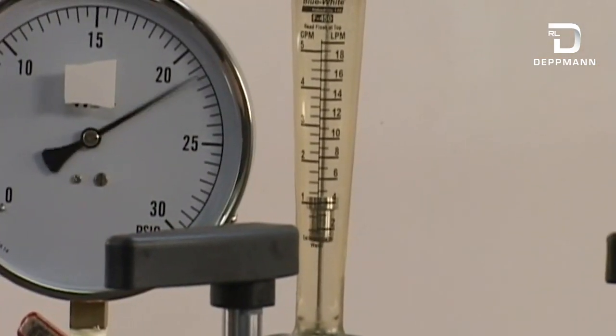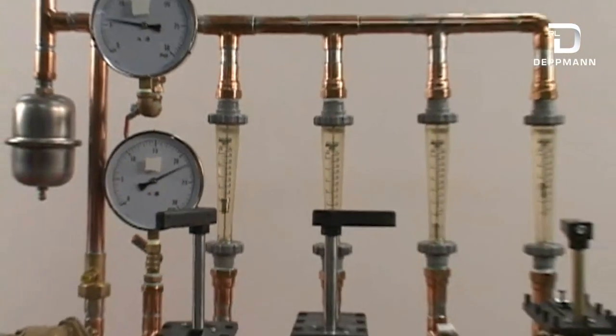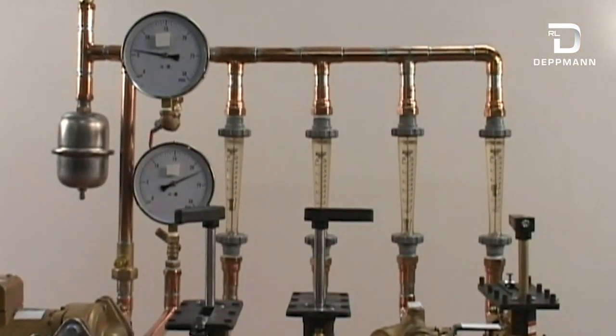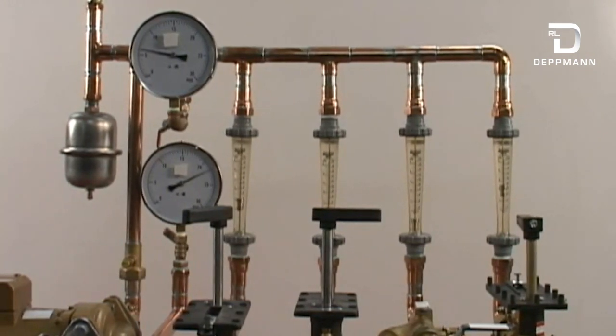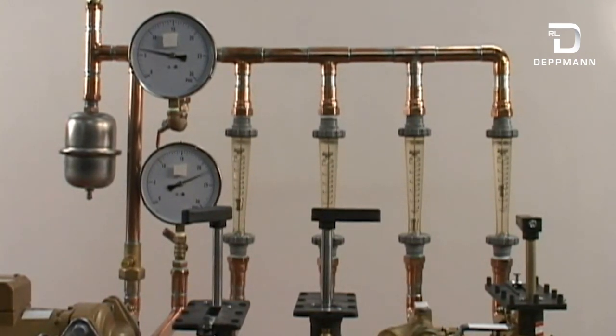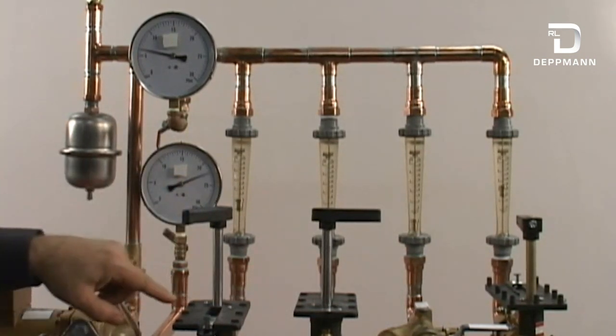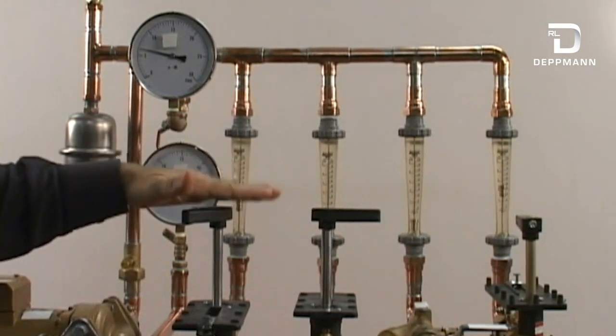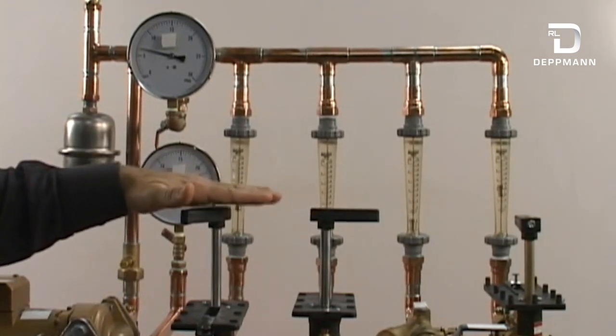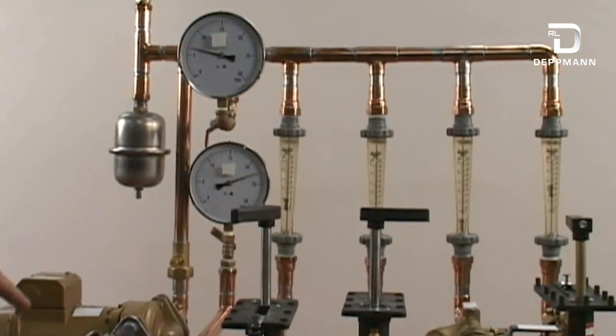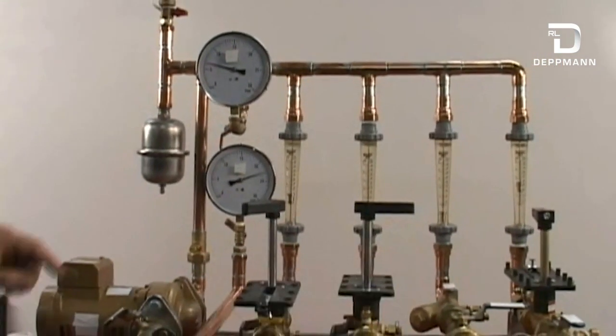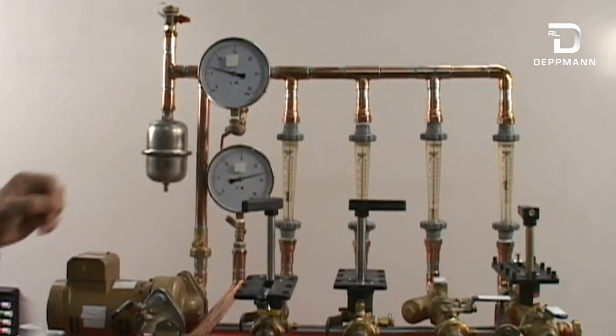Now it's starting to become later at night, we're going to need some heat. So I'm going to simulate a pressure increase by ramping up this variable speed pump. And what you're going to see is that this pressure independent valve, if no signal tells this valve to change its position, even though I'm going to ramp the RPM up and force more water through these other zones, you're going to see this is going to stay at 1 GPM.